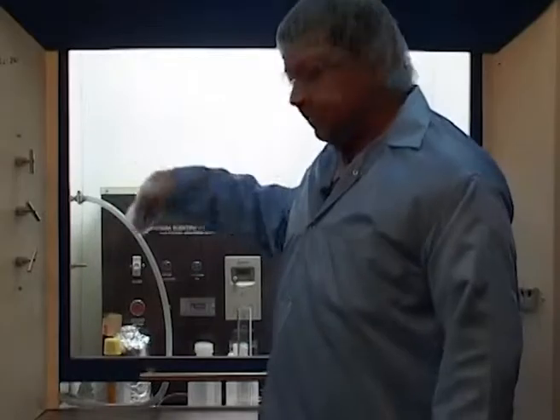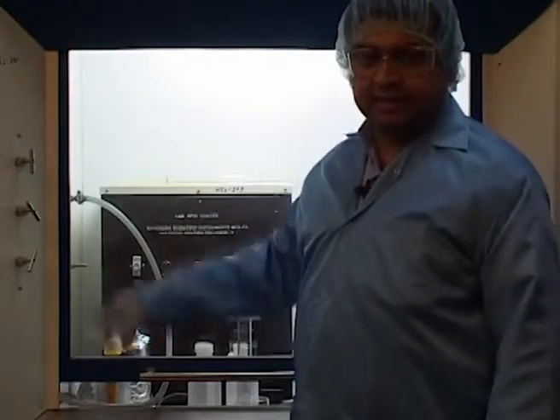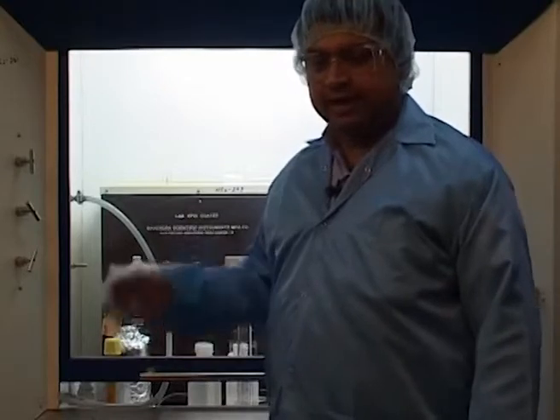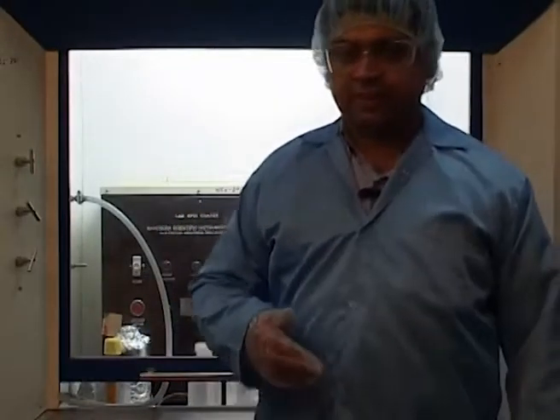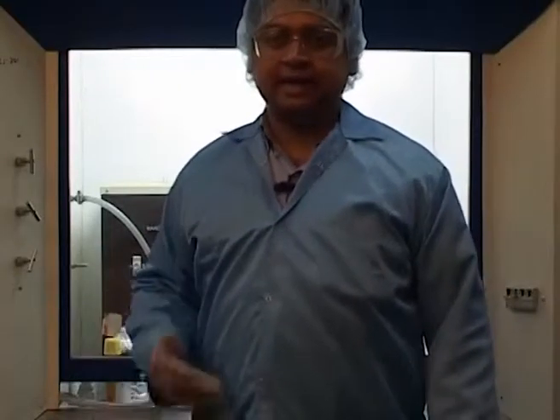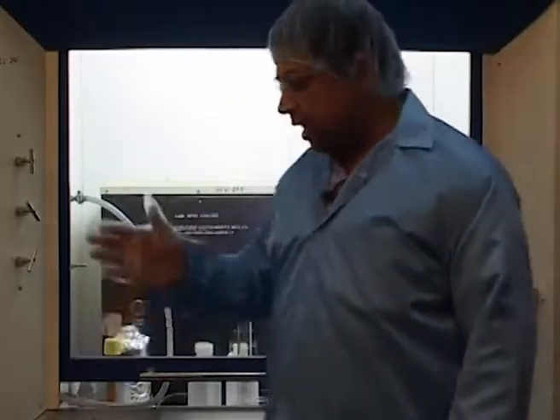This right here is one of the fundamental components used in such a laboratory. It is known as the fume hood. Essentially it provides a class 1000 clean space, which is just underneath or behind this particular panel. There is a blower unit which circulates and causes a laminar flow of air inside this hood, so that all the dust around passes through a set of HEPA filters and the air is recirculated back, and there is absolutely no entry of dust particles from outside into the clean space. Most of the dust particles exit because of this continuous laminar flow operation.